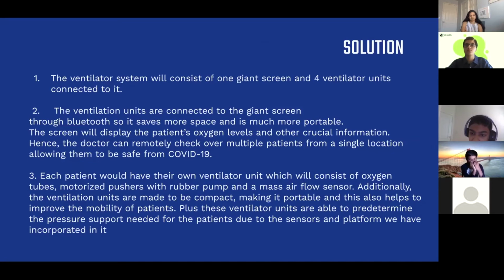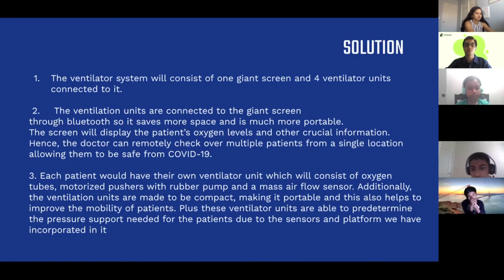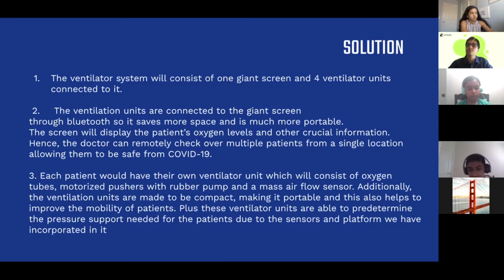Our ventilator system will consist of 1 giant screen and 4 ventilator units connected to it. The ventilator units are connected to the giant screen through Bluetooth, so it saves more space and is much more portable. The screen will display the patient's oxygen levels and other crucial information. Hence, the doctor can remotely check multiple patients from a single location, allowing them to be safe from COVID-19. Each patient would have their own ventilator unit, which will consist of oxygen tubes, motorized pushers with rubber pump, and a mass airflow sensor. Additionally, the ventilation units are made to be compact, making it portable, and this also helps to improve the mobility of the patients. Plus, these ventilators are also able to predetermine the pressure support needed for the patients due to the sensors and platforms we have incorporated in it.